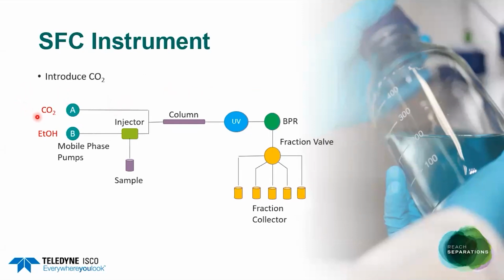Okay, if we now exchange the hexane portion of the mobile phase for CO2, we're now getting something closer towards an SFC system. When we do this, we then need to introduce a back pressure regulator later on in the system, as depicted here, and that's to maintain the CO2 in its supercritical state. What's not on this slide as well is that we also need to keep the injector, the column, and the mobile phase at an elevated temperature to keep the CO2 in its supercritical state.